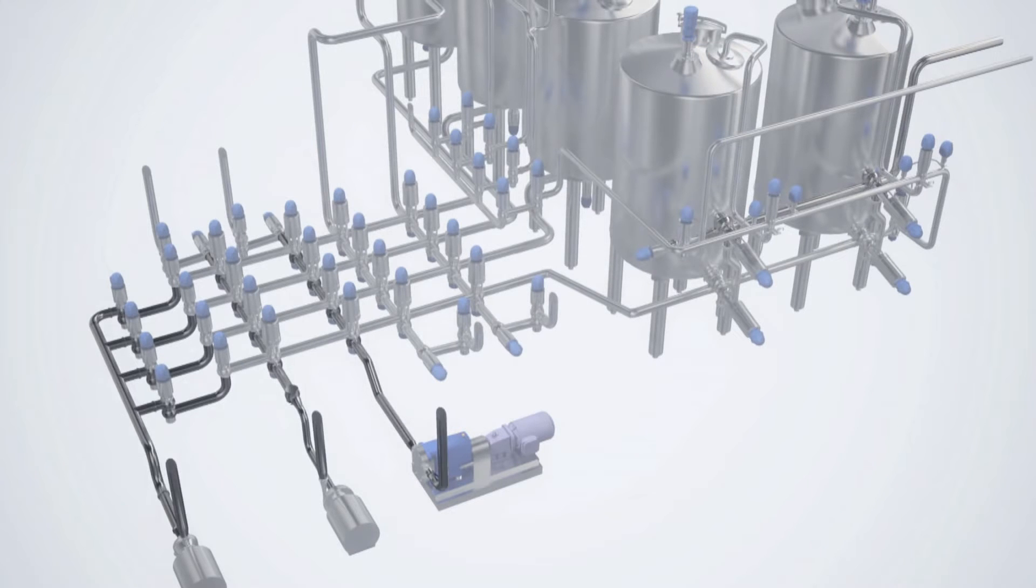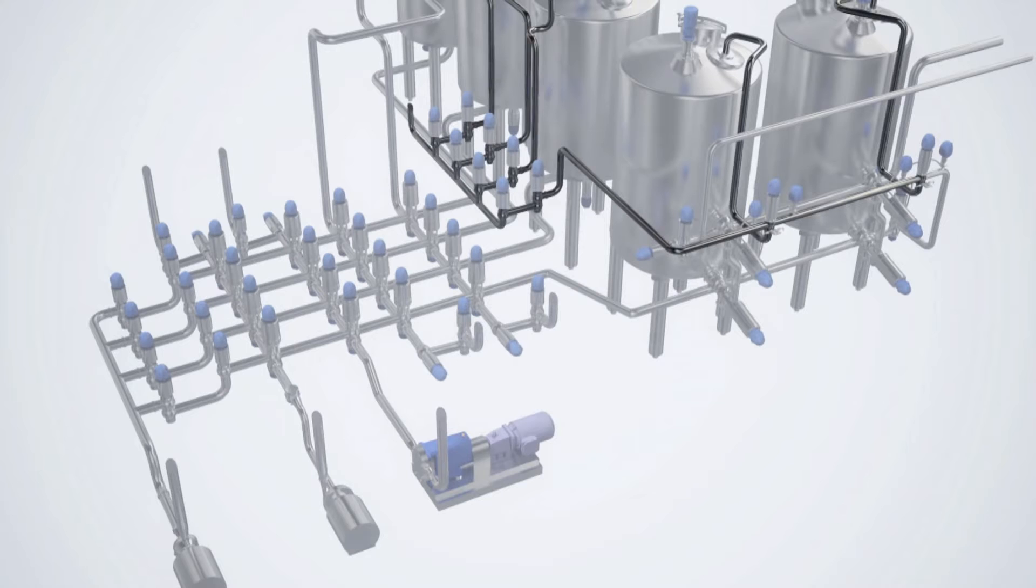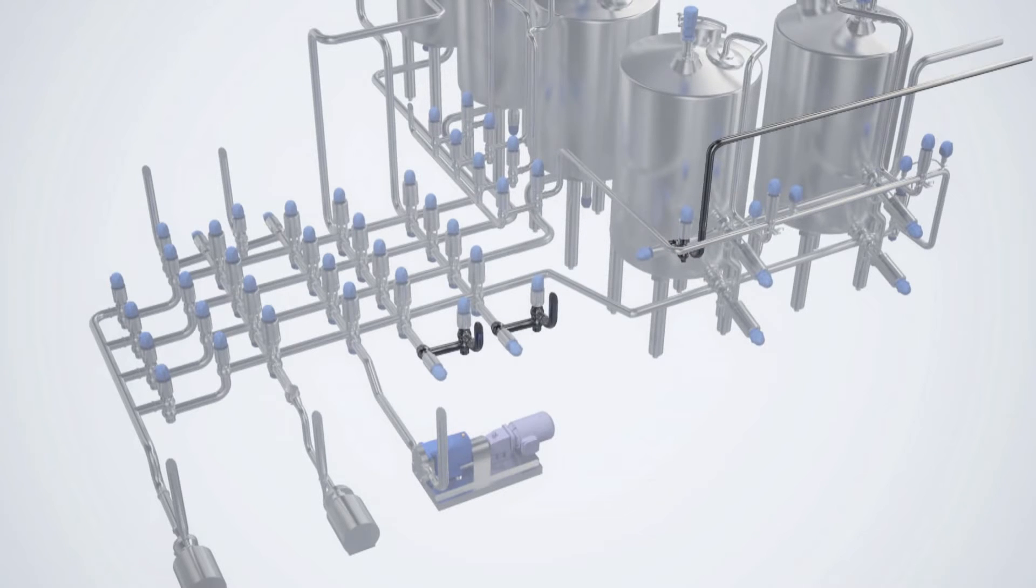There are three destinations including one common CIP return line. Destinations could be fillers, pasteurizers, or blend systems. All five tanks share a common CIP supply line. The product supply line is equipped with CIP return valves and the product destination lines are supplied with CIP forward valves.